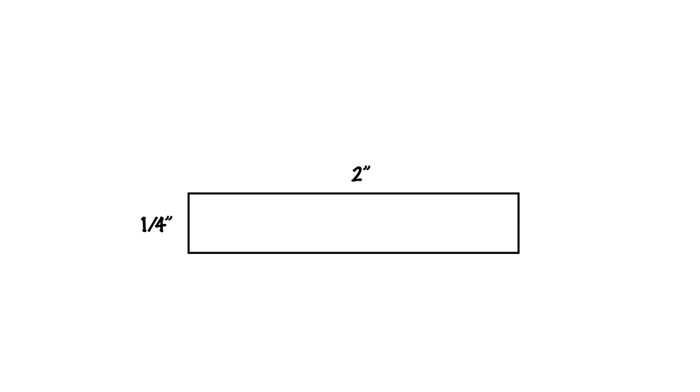In this video, we'll be walking through how to calculate the square mil area, your SMA, of a conductor, and then convert it to CMA if you need to. So what we have here is your basic bus bar. This one is 2 inches by 1/4 inch.